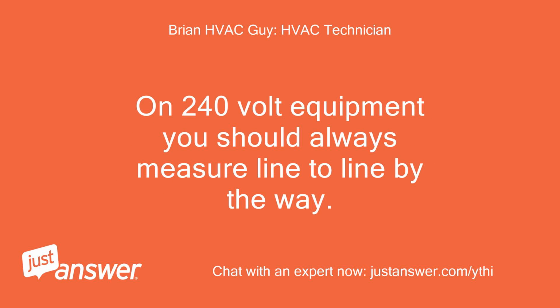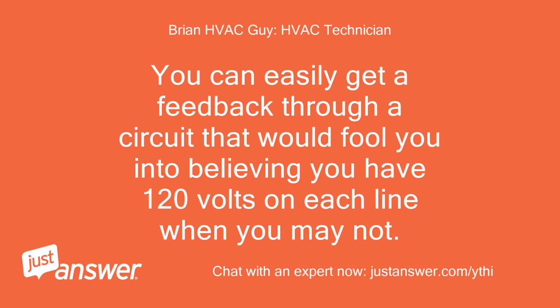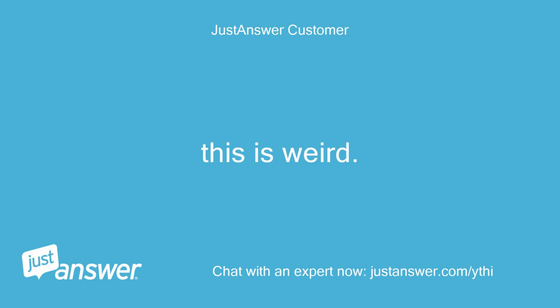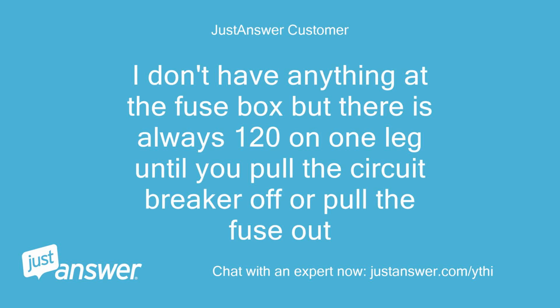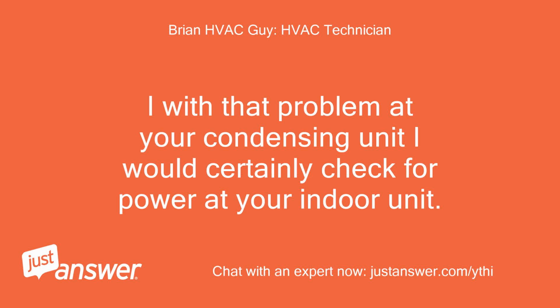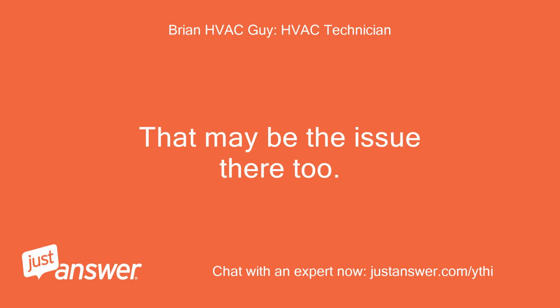On 240 volt equipment you should always measure line to line, by the way. You can easily get a feedback through a circuit that would fool you into believing you have 120 volts on each line when you may not. This is weird. I don't have anything at the fuse box, but there is always 120 on one leg until you pull the circuit breaker off or pull the fuse out. With that problem at your condensing unit, I would certainly check for power at your indoor unit. That may be the issue there too.